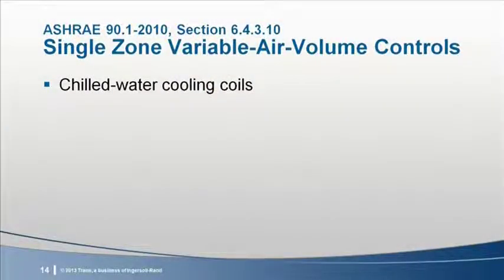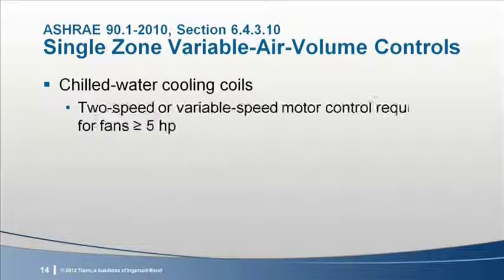This section contains two parts. The first part addresses systems that use chilled water for cooling, and the second part, which we'll look at next, addresses systems that use direct expansion. Part A addresses air handling units and fan coils with chilled water cooling. The standard requires variable airflow controls if the supply fan is 5 horsepower or larger. For systems in this size range, the supply fan must be controlled by either a 2-speed motor or a variable speed drive. The standard does not require fully variable airflow, as might be achieved with a VFD.